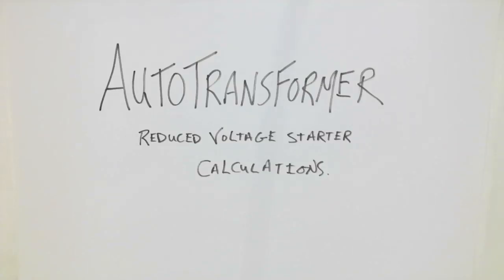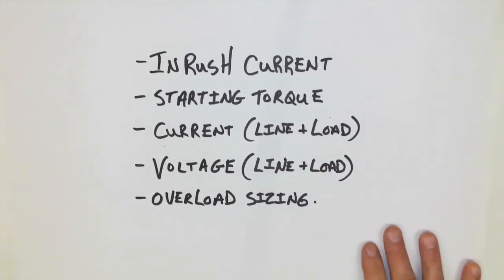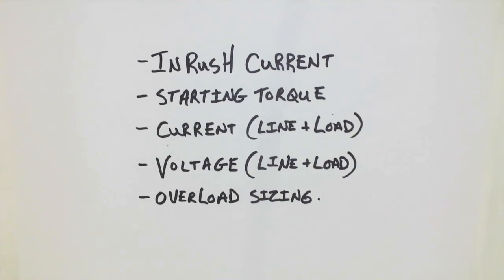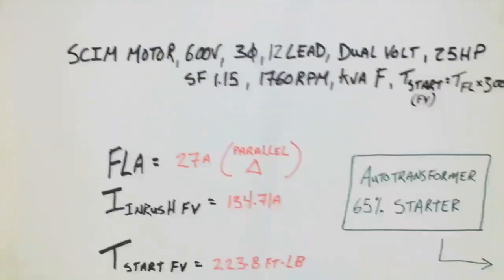Autotransformer reduced voltage starter calculations. In this presentation, we're going to be looking at the inrush current, starting torque, current on the line and load side of the starter, voltage on the line and load side of the starter, and the overload sizing for an autotransformer reduced voltage starter.